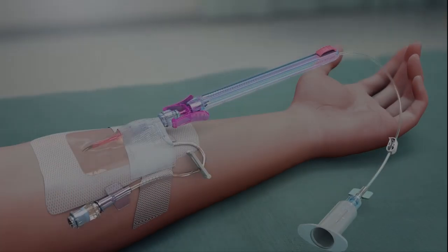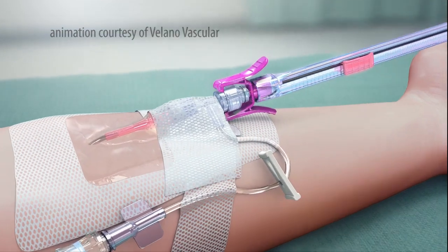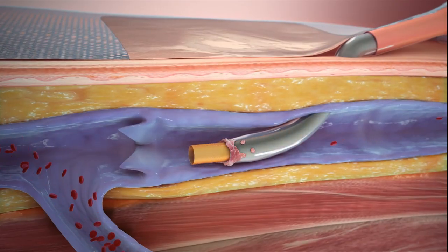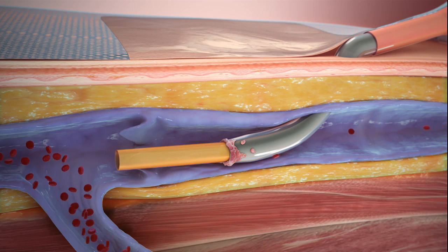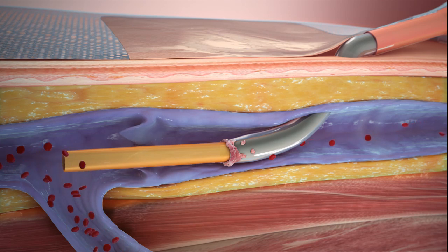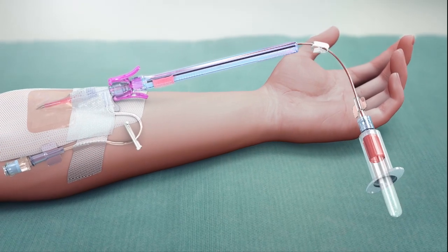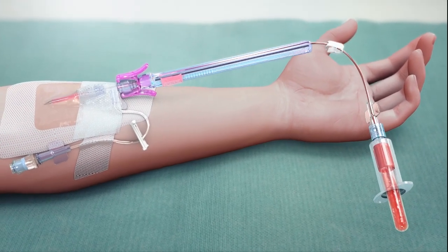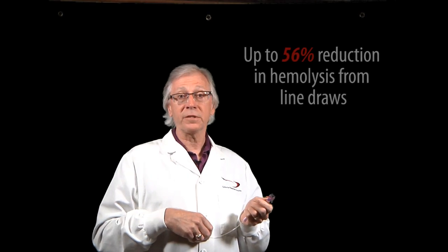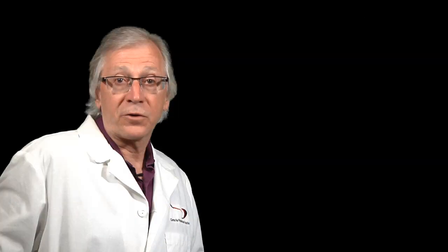Or you can implement technology designed specifically for drawing from peripheral lines. After the line is flushed, this device attaches to the luer of the IV set and a flexible internal flow tube is advanced through the cannula beyond the catheter tip — where hemolysis usually occurs — and to a point where the blood flow is more normal. Then the collector simply withdraws the sample as for any other draw. Once the tubes are filled, the device is removed and the line is flushed again.